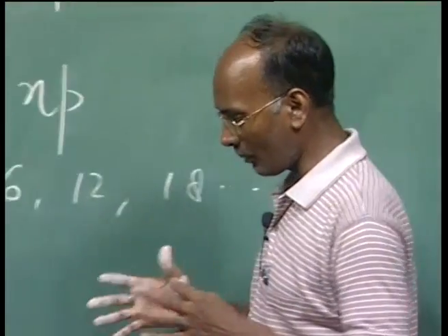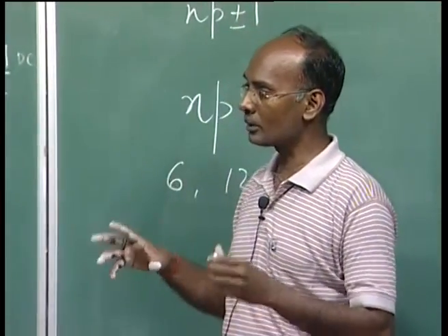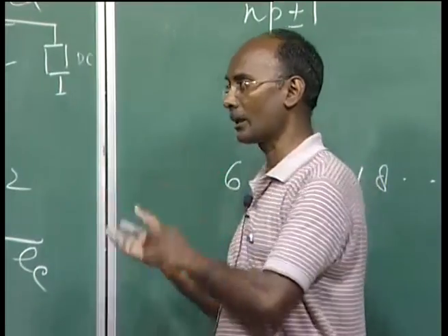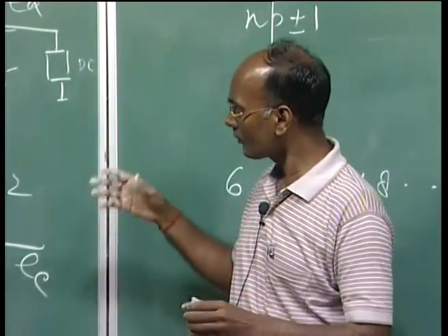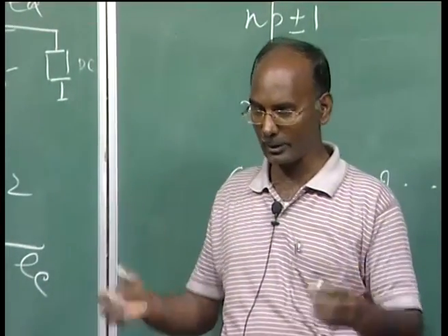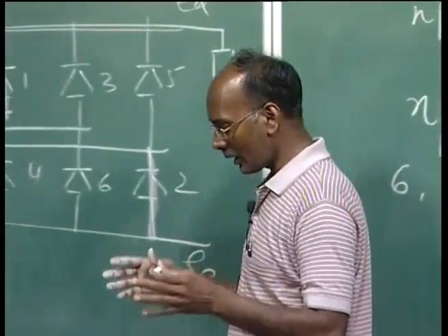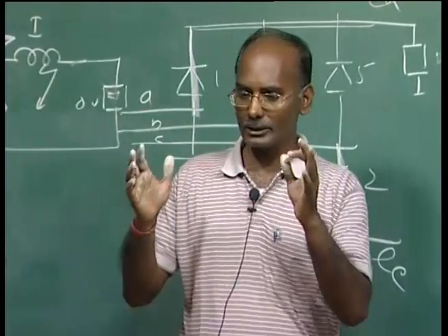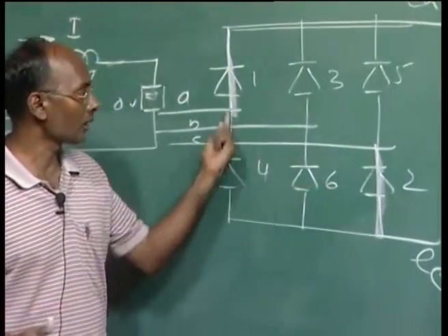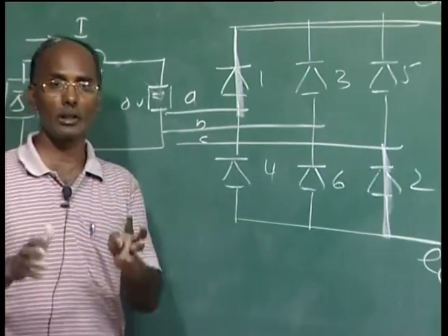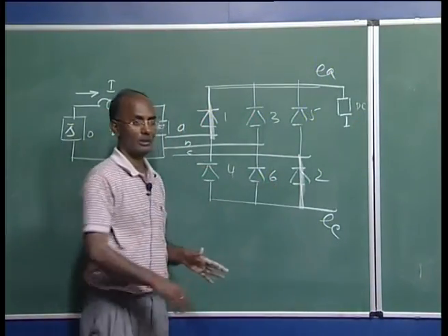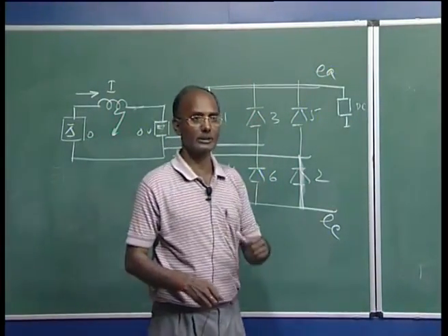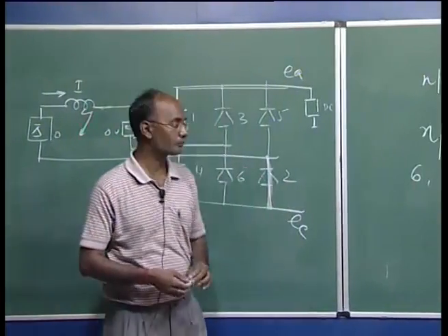We saw the converters, which are the major part of this HVDC transmission system. We are going to have two converters, one at the rectification end and one at the inverter end, if it is a 2-terminal HVDC system, or we can go for 3 terminals. If we are going for a 3-terminal HVDC, then we require 3 converters. And the converter, as a whole, I mentioned as a broader category, is not a simple bridge converter. We require the controllers of these thyristor valves as well, and that is a very special part of this converter. So the converter means this bridge converter along with its controller. The controller is a major portion, which we will discuss in a dedicated module on the controller itself.